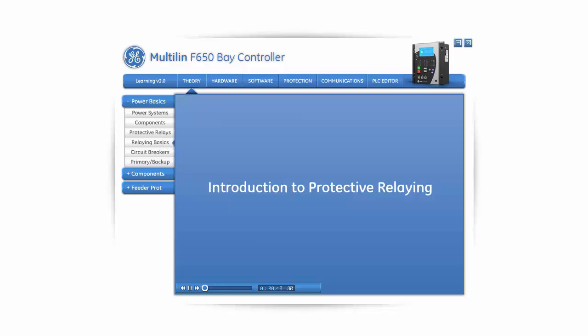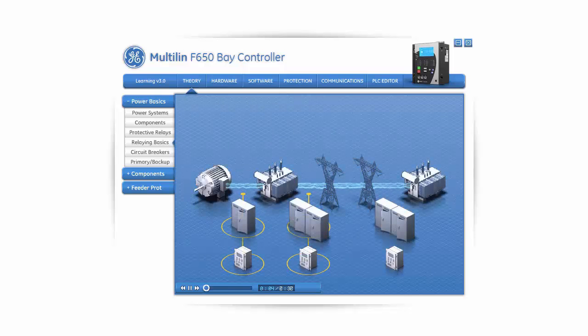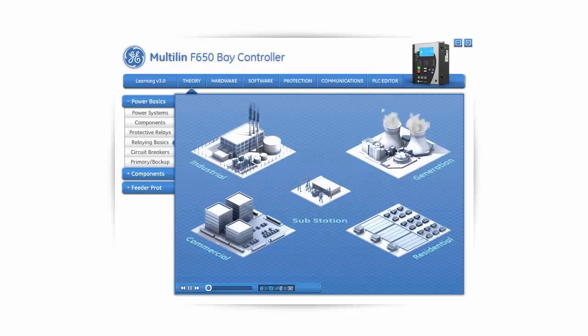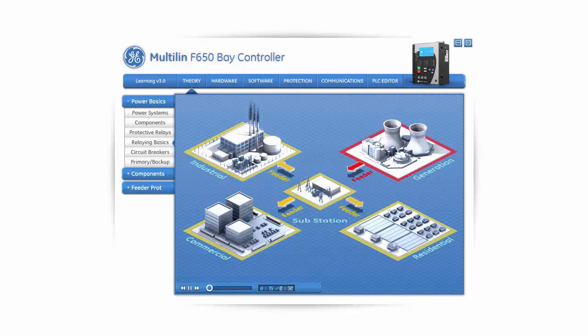The function of protective relaying is to immediately remove any component of a power system when it suffers a fault that might result in damage to property or present any unsafe conditions. In addition, protective relays can provide information on the locations and types of failures that occur. This information not only helps with equipment repair, but also provides the means for analyzing the effectiveness of the protection scheme. We should note that protective relays are not always part of a protection scheme.